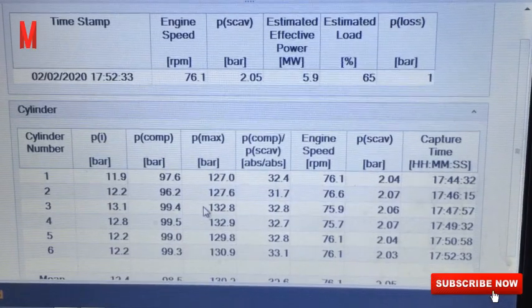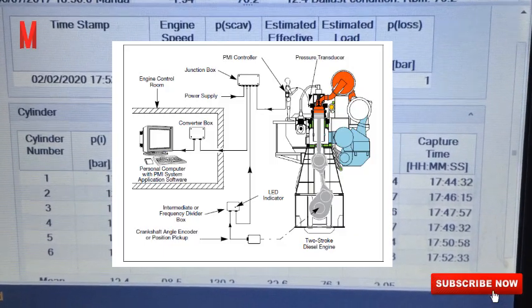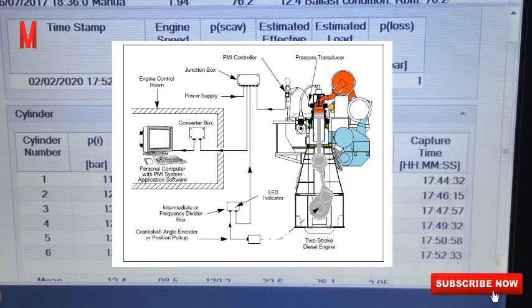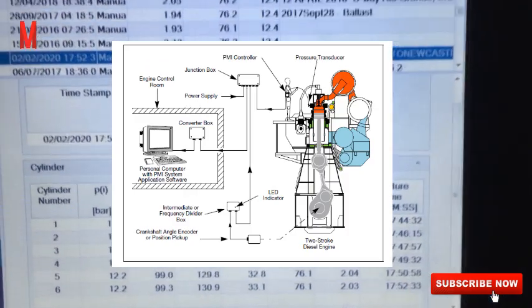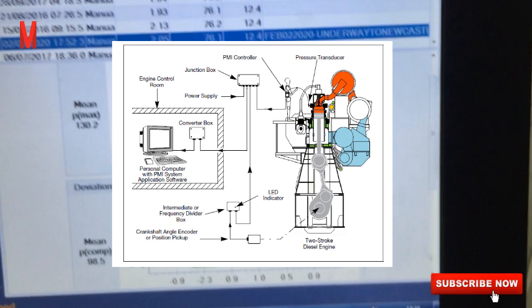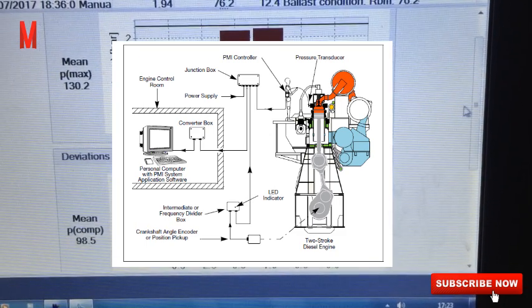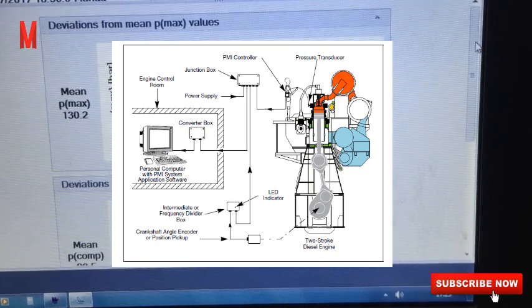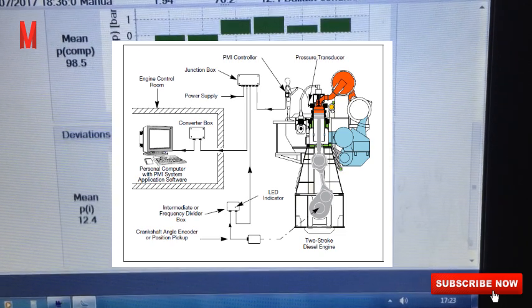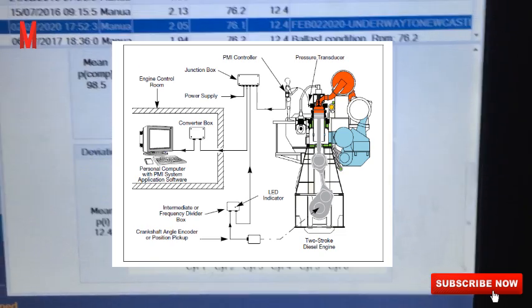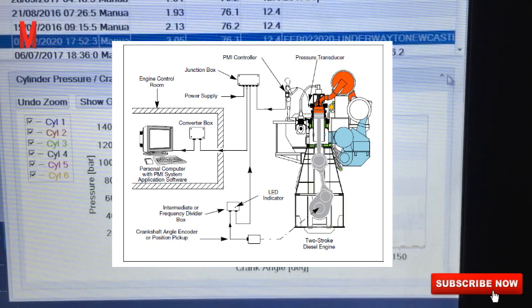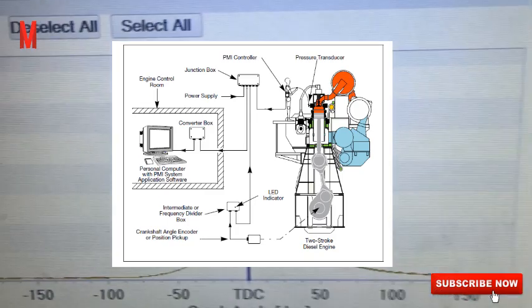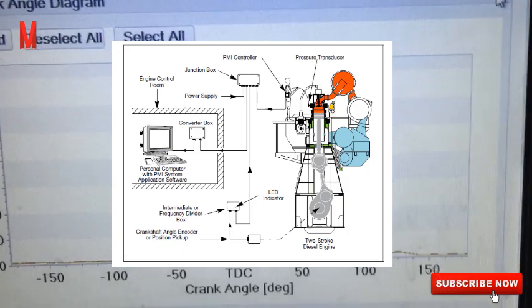The schematic diagram shows that from the main engine we have the pressure transducer and the PMI controller, the junction box, and the computer PMI system. The offline version of the system employs a high-performance piezoelectric transducer. This is a well-proven design which is mounted on the cylinder head indicator cock, from which the cylinder pressure is measured.